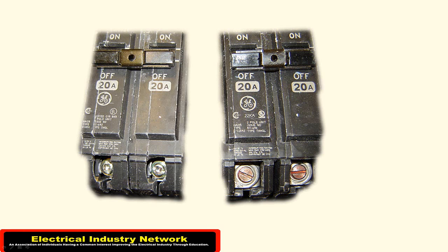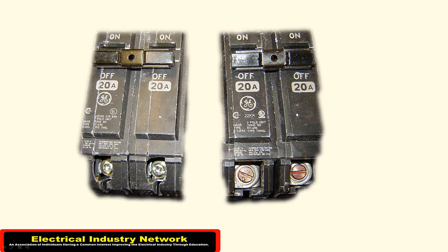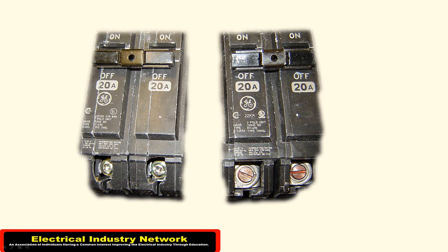The only other visual that I could tell is the type of screws and types of lugs that they have here. This particular lug just doesn't seem as heavy duty as this one does, and that could be the AIC rating—I'm not 100% sure on that—but when we went to get the straight 240s, we couldn't, we had to get 22k anyway, so this is what I came up with.